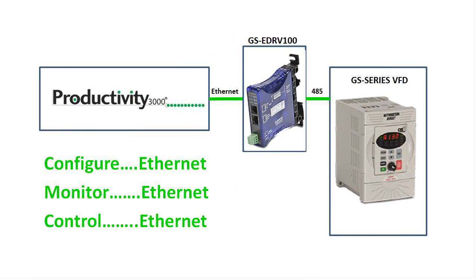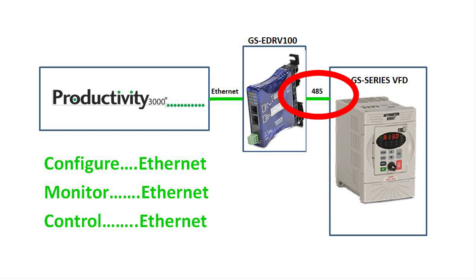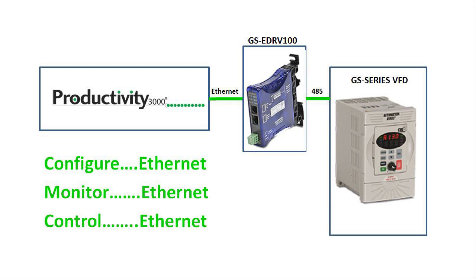The nice thing about controlling the drive over the network is you only have two possible failure points: the network connection between the controller and the GSE drive and the 485 connection between the GSE drive and the VFD. And the Productivity 3000 makes it easy to monitor, diagnose and gracefully control the motor shutdown should either of them fail.